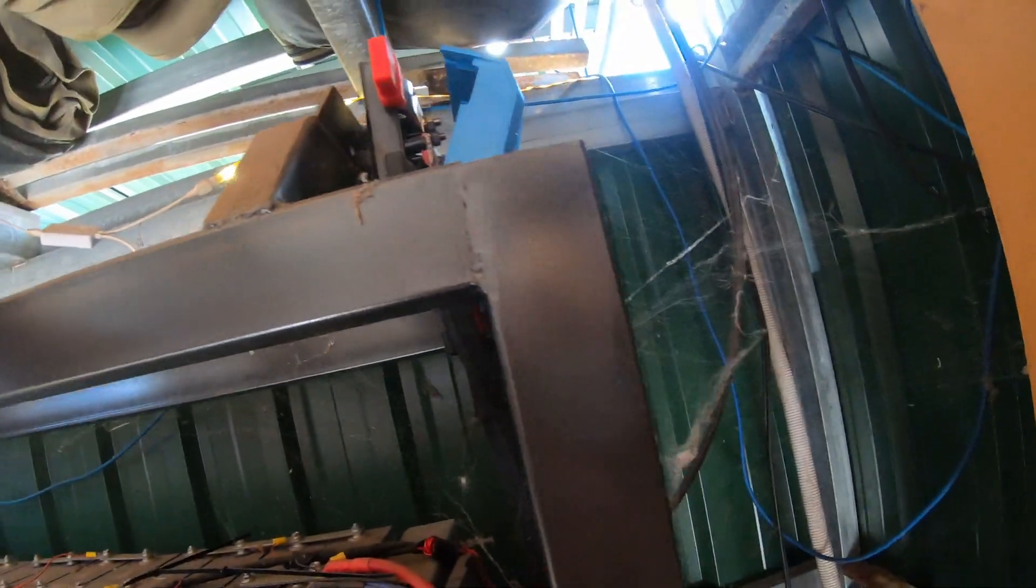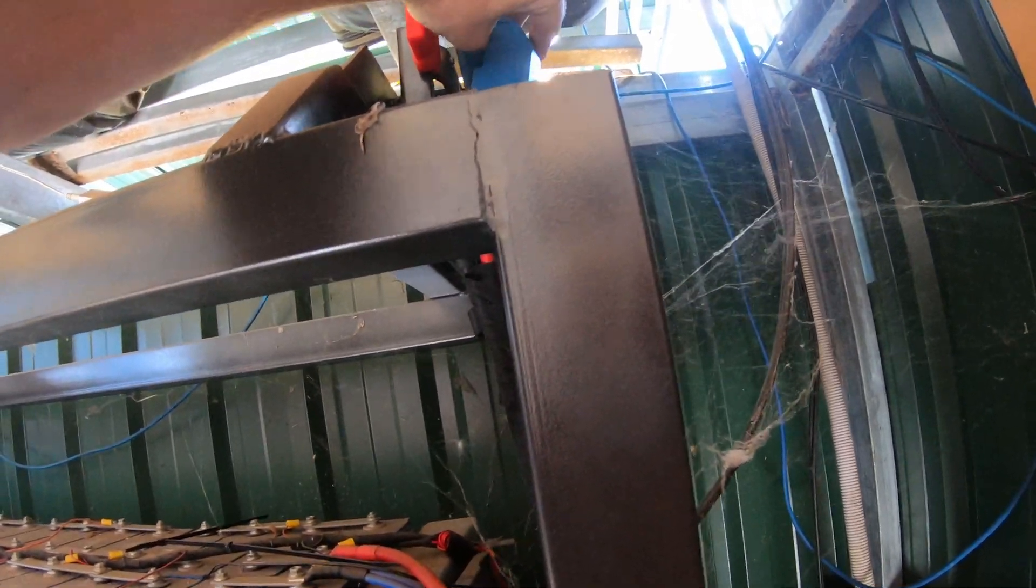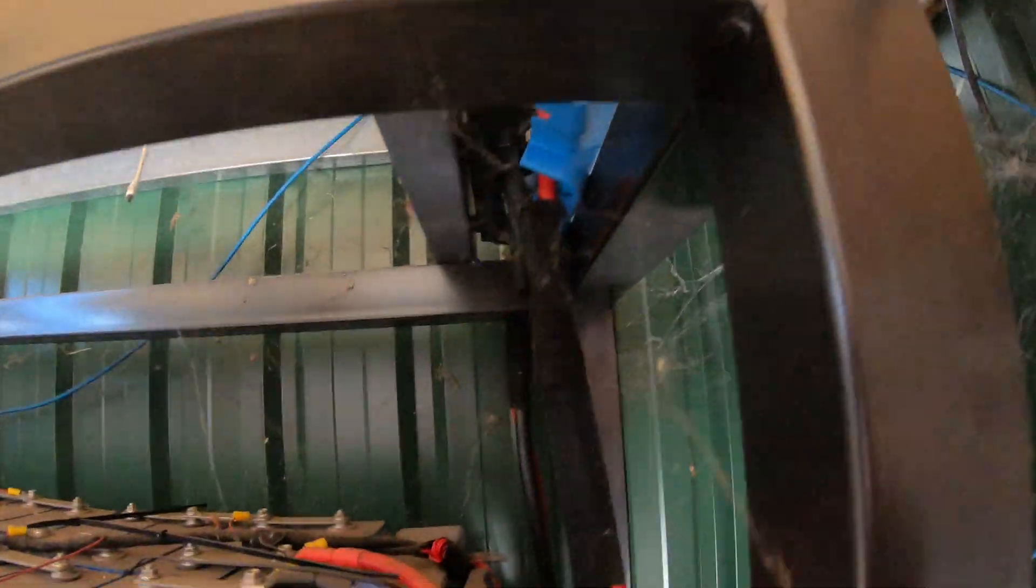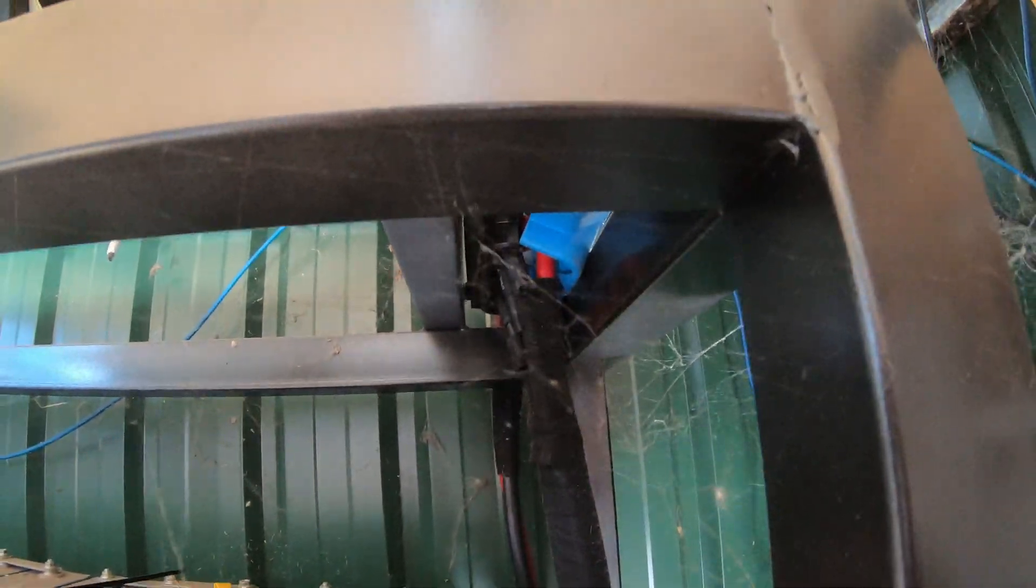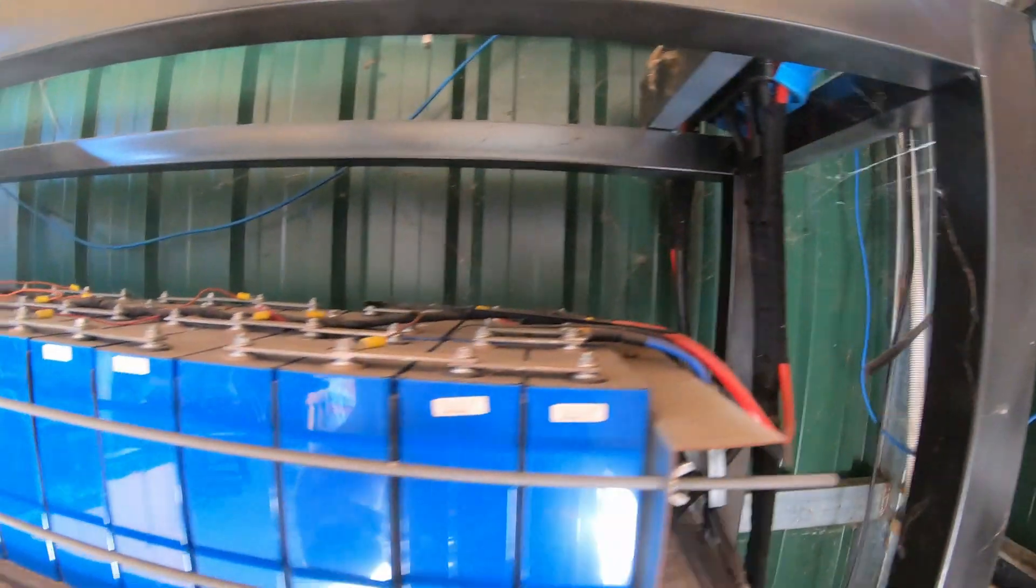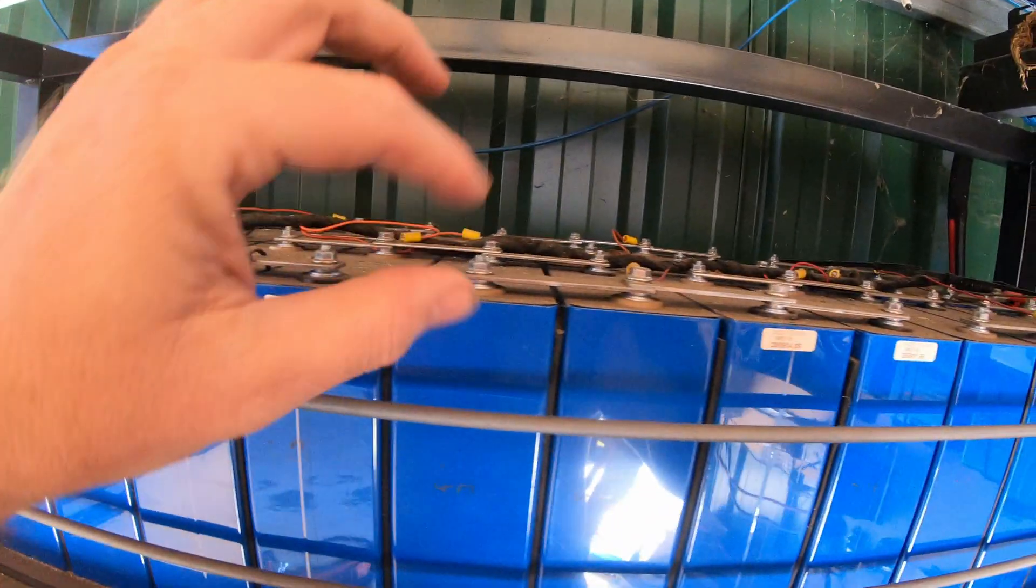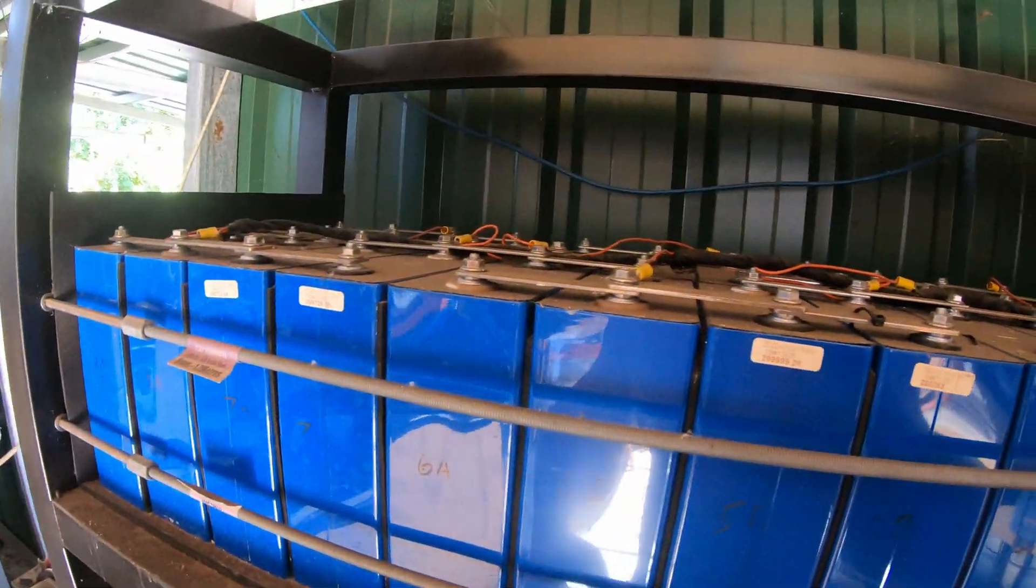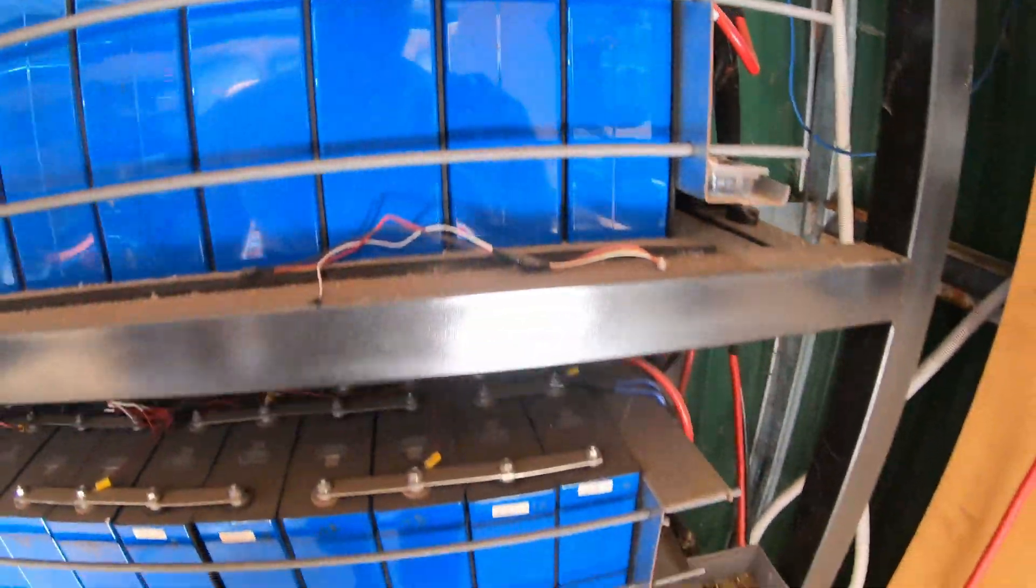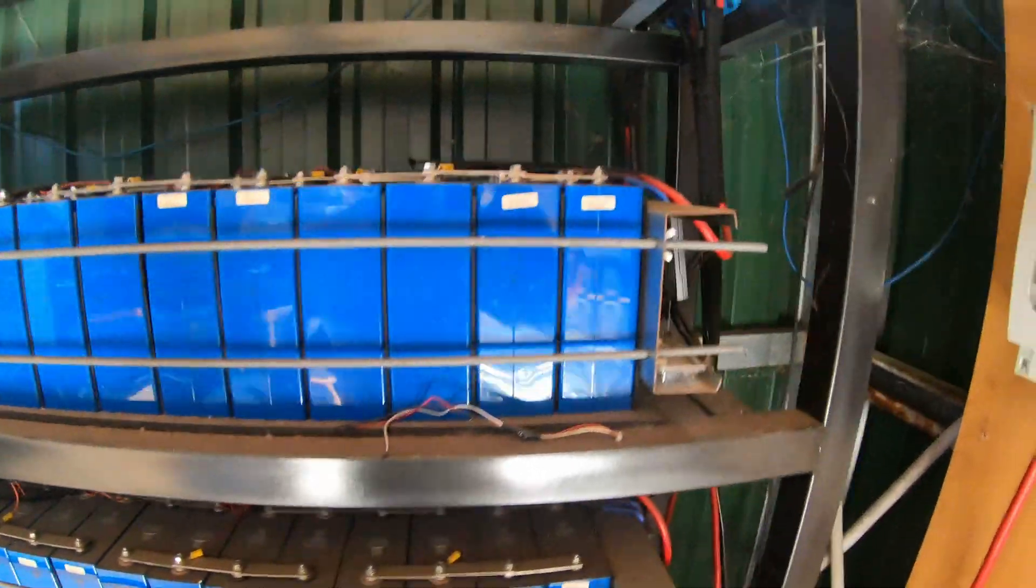One thing I haven't done for a while - and it's part of the reason why these screws are loose - is getting in there and tightening those things up. But because of how tight that is in there, it's actually really difficult to get that cover out. Generally, once a year I try to come in here, and as these things expand and contract over winter I've found a couple times some loose nuts. I usually come in here and look over it with my infrared camera to make sure they're all okay.